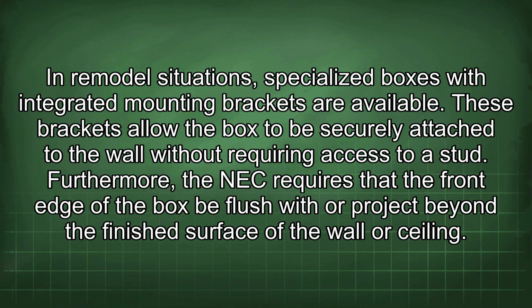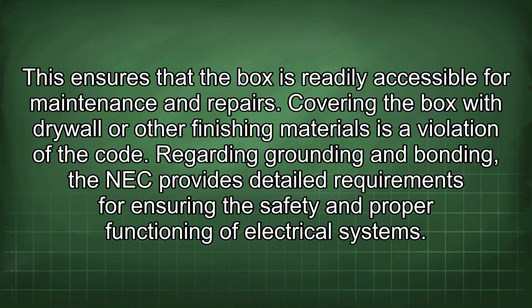Furthermore, the NEC requires that the front edge of the box be flush with or project beyond the finished surface of the wall or ceiling. This ensures that the box is readily accessible for maintenance and repairs. Covering the box with drywall or other finishing materials is a violation of the code.